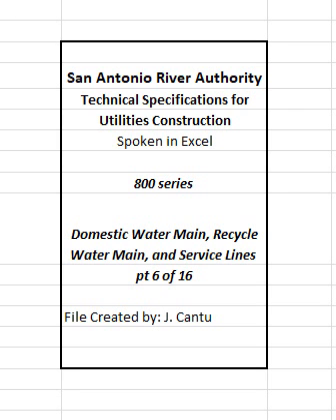3. Construction methods. A. Excavation. Excavation and trenching, as required to complete the water main installation, shall be as outlined herein, as shown on the plans and as directed. Blasting to perform the excavation is not allowed. 1. Trenches. All excavation shall be to a depth to provide a minimum of 4 feet of cover over the top of the pipe unless otherwise shown on the plans or authorized in writing by the engineer.